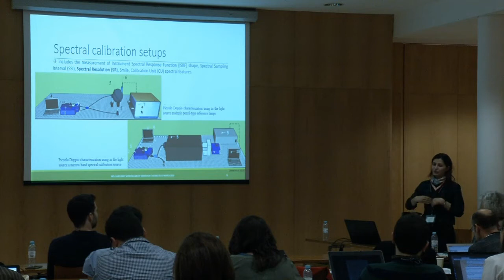So coming back to using reference lamps, the method that is used by Ocean Optics, for example, so by the producers, is that practically you measure the signal of this kind of lamps. You will obtain a spectra like that. You apply a Gaussian fit for each peak, you obtain a central wavelength, and knowing this center wavelength, you apply a third-order polynomial fit. In this way you have the correction coefficients for the position of each pixel. So for each pixel you have the corresponding wavelength.